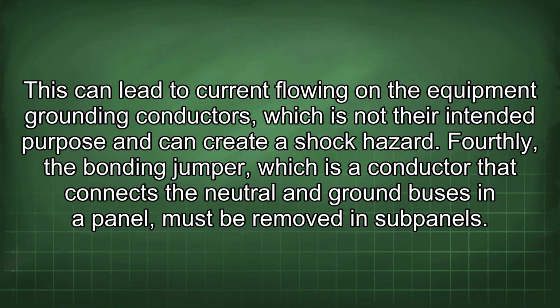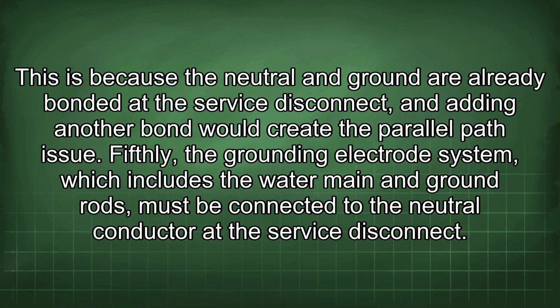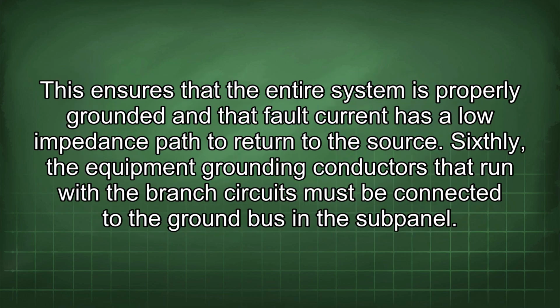Fourthly, the bonding jumper, which is a conductor that connects the neutral and ground buses in a panel, must be removed in subpanels. This is because the neutral and ground are already bonded at the service disconnect, and adding another bond would create the parallel path issue. Fifthly, the grounding electrode system, which includes the water main and ground rods, must be connected to the neutral conductor at the service disconnect. This ensures that the entire system is properly grounded and that fault current has a low impedance path to return to the source.